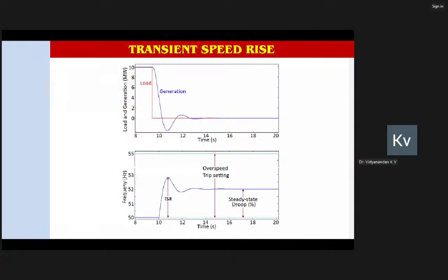Transient speed rise is whenever there is a sudden drop in the electrical load, like a generator breaker opening, or maybe a transmission line tripping. Suppose from your switchyard station there are 3 lines going out, and suddenly one line trips, so 2 lines are there. Naturally the electrical load on the system has reduced, and that will result in acceleration of the prime mover.